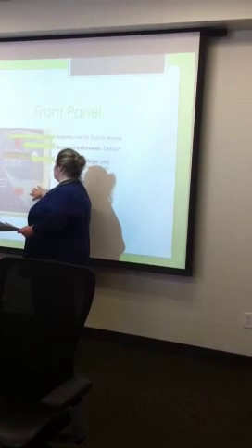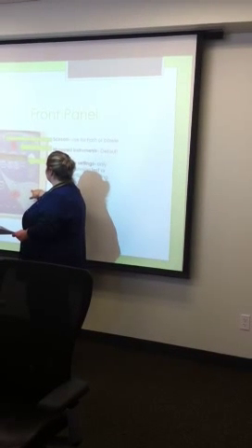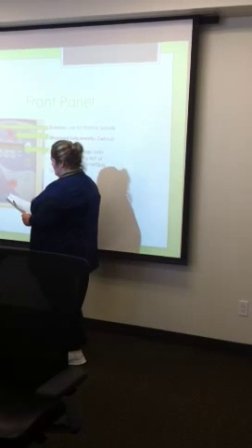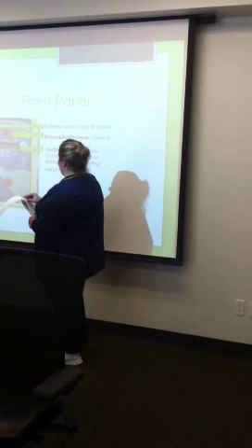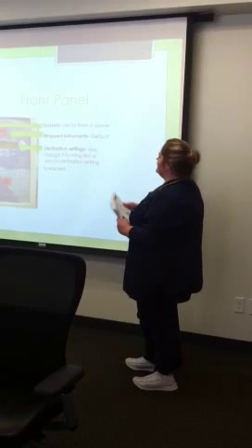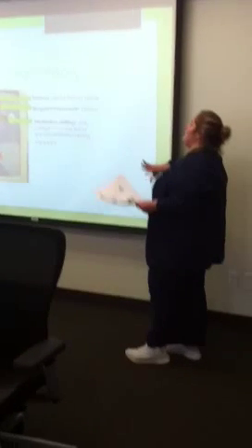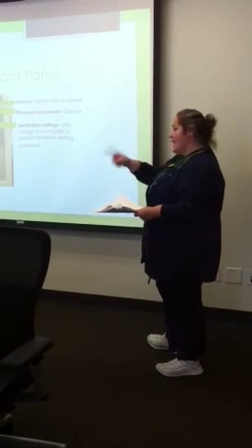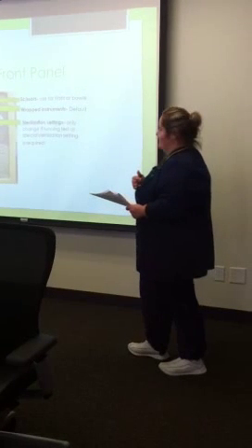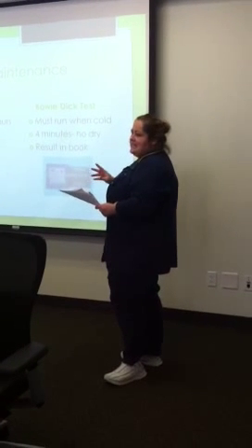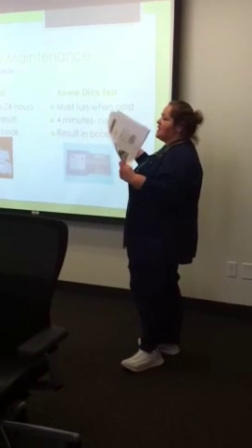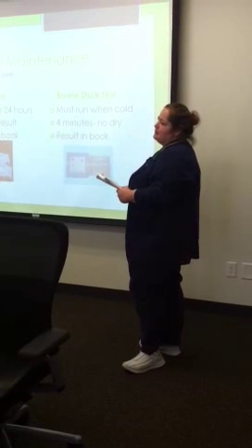This one here is used when we are doing the monthly maintenance on it, so you don't need to worry about that. That's just letting water into the machine. And there's your start button. Down here is your door close button. We've gone back and forth on how tight to close the door. We were originally told tighten it until the light comes on and that's good enough. Then we were told tighten it a little bit more, and then we were told finally that it should be hand tight. Not Jason hand tight, because then we can't open it. But when the light comes on, it's not good enough. So what's happening was the steam was coming up, and we were continuously running out of water in the machine.